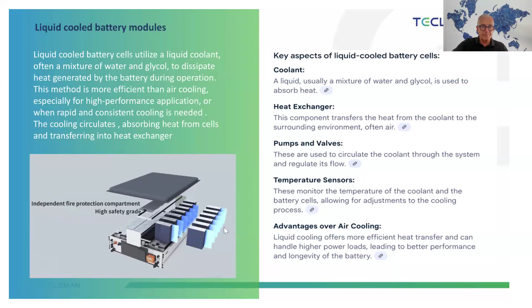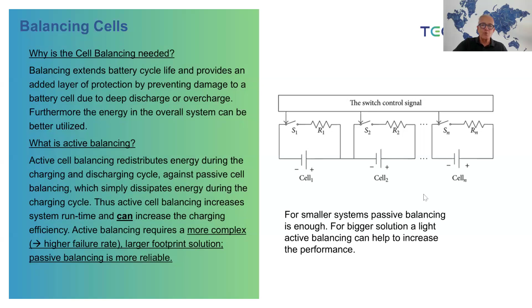It's better to use liquid cooled batteries. The reason is, if you don't use it, you need active balancing. All normal air-cooled systems use active balancing, because it brings additional capacity to very weak battery cells due to temperature problems, but then you lose capacity from your storage system. With liquid cooling, you don't need big active balancing, only normal passive balancing is necessary, and you don't lose capacity or suffer degradation. So even if you plan to install a storage system in the future, every storage system should have liquid cooled battery cells inside.